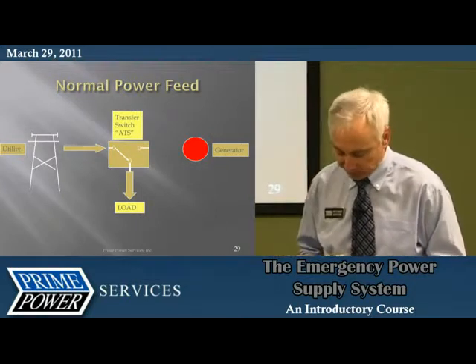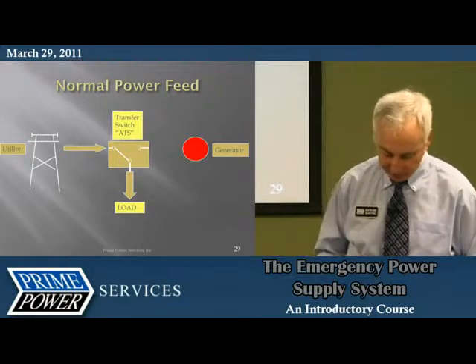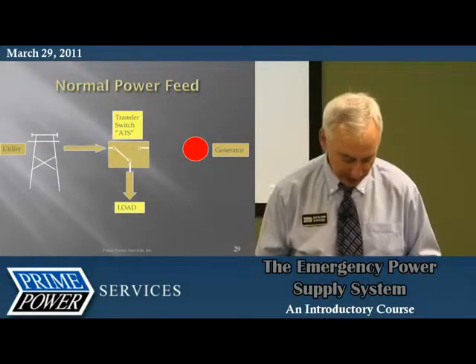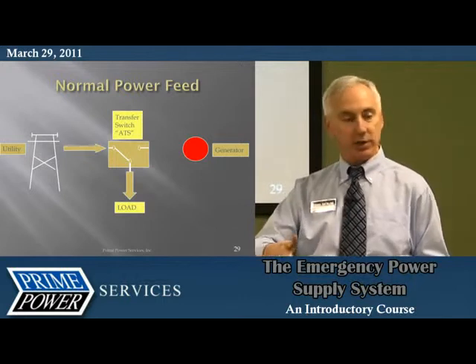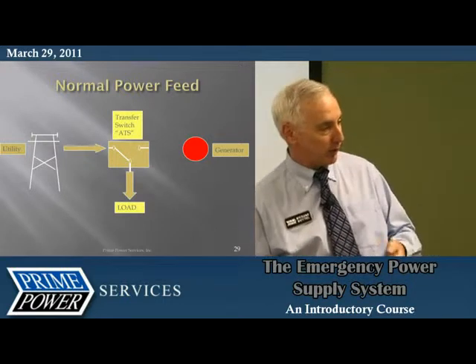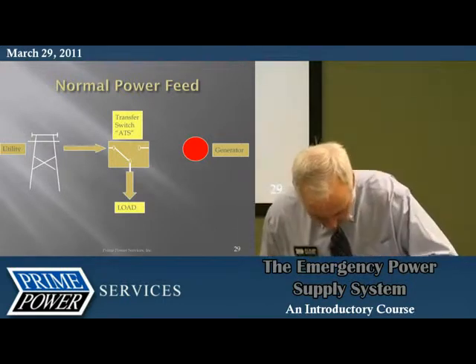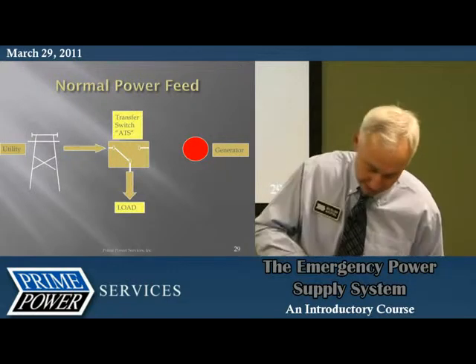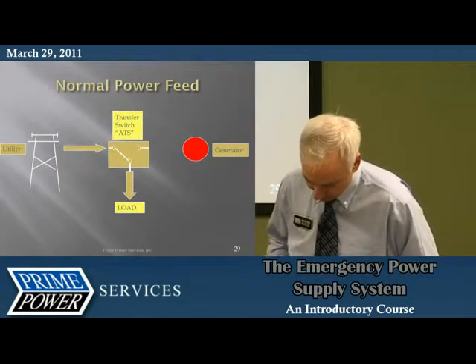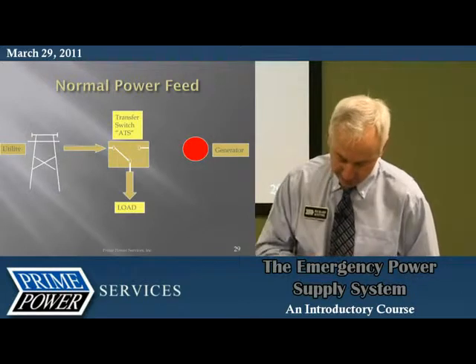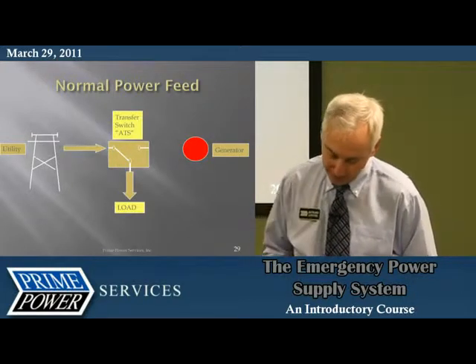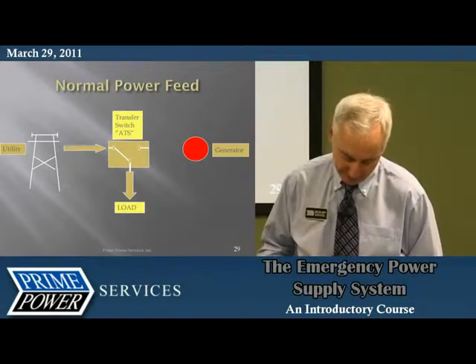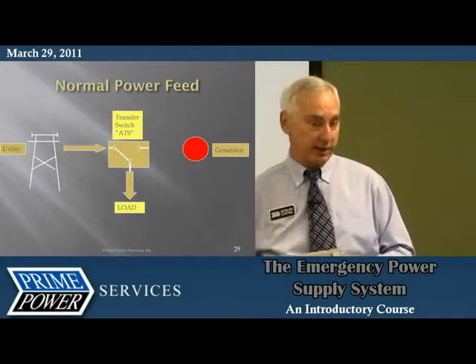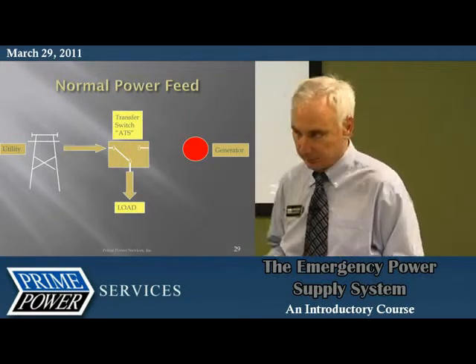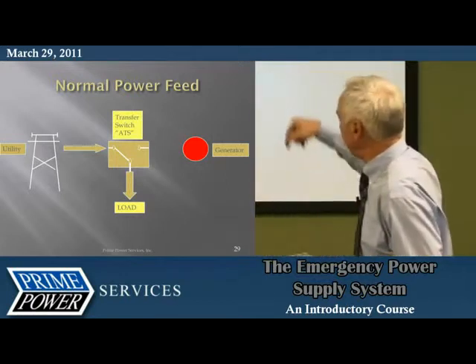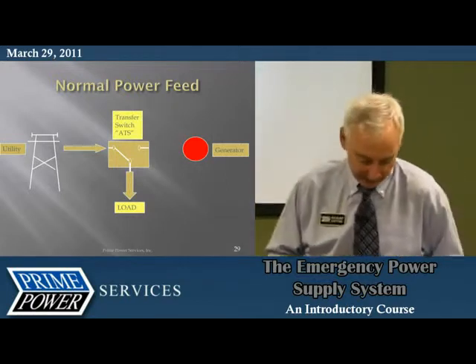What it is, we have two sources coming in. We have emergency down here, we have normal up here. Then you see this flexible connector. Depending on where this movable contact is, it's either going to connect to the utility side or the generator side, either one, and then it'll go out to this load. So that's exactly what we've got right there.